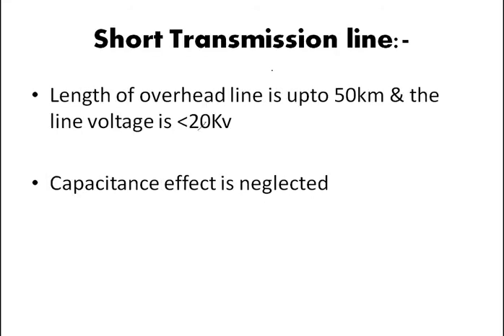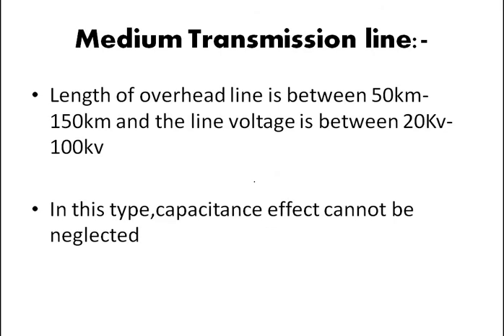The first one is short transmission line. The length of the overhead line is up to 50 kilometers, and the line voltage is less than 20 kilovolt. The capacitance effect in short overhead line is neglected because of the small length and low voltage. Therefore, while designing, modeling, and studying the performance of short line, only resistance and inductance are taken into account.